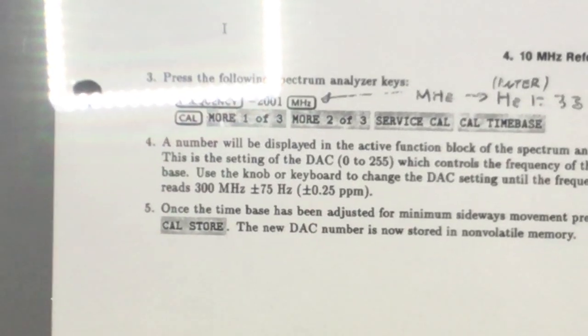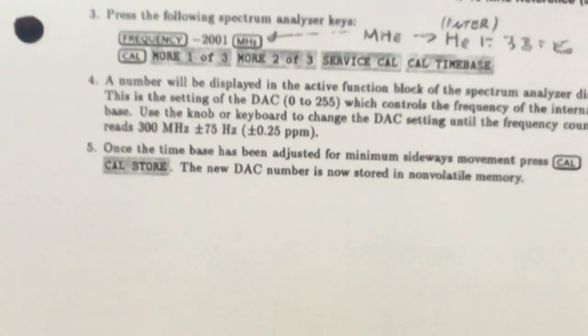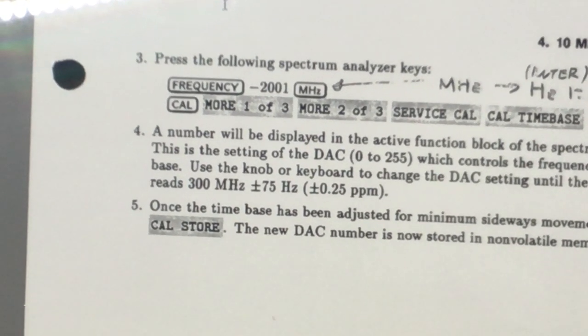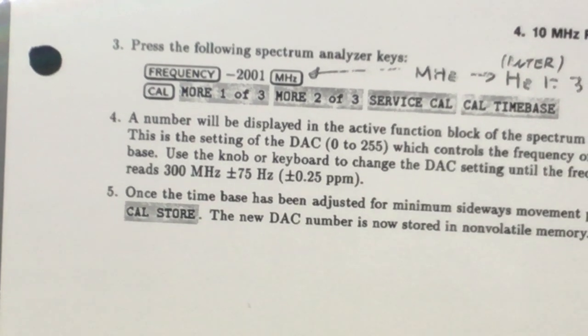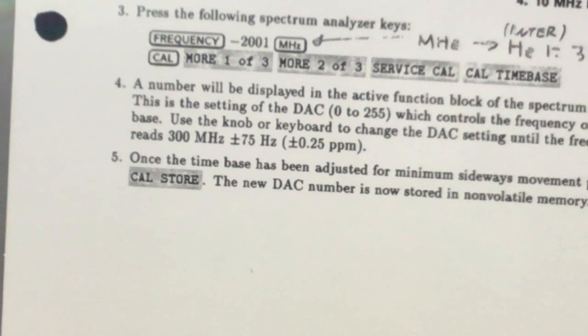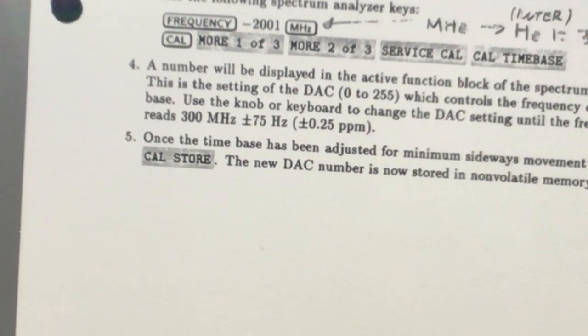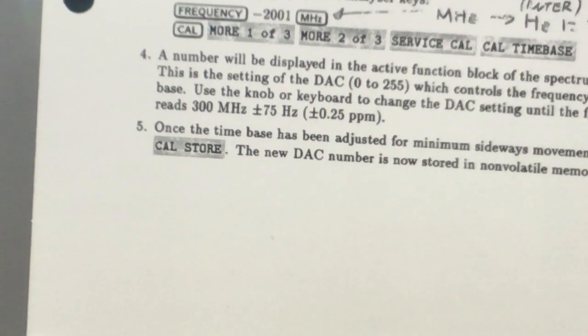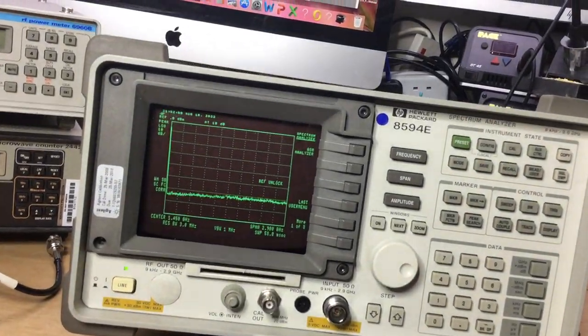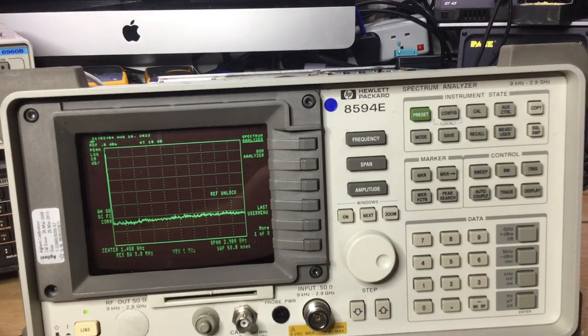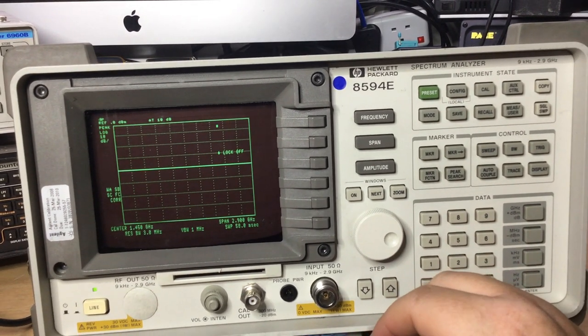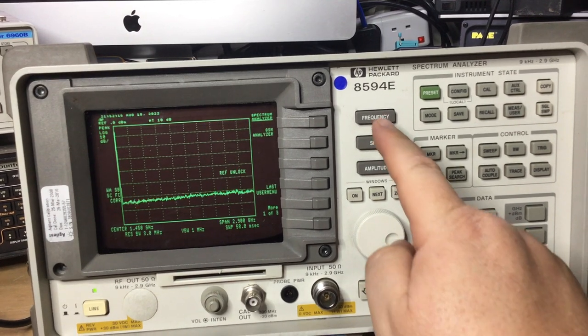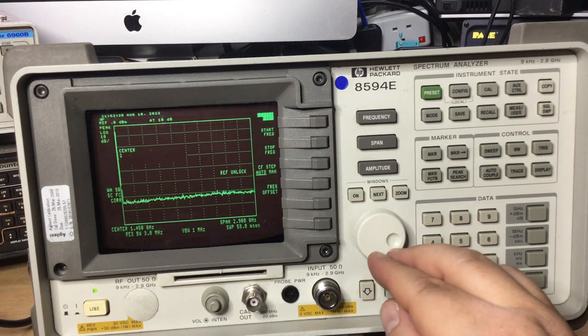Okay, to access the calibrate in the service manual, it talks about using a frequency, excuse me, as a prerequisite, -2001 megahertz. And then going to the service cal and then selecting the time base. Now, when we do that, then a DAC number will appear on the screen and we can adjust that accordingly to then calibrate the frequency. So we'll just look at that now then. So what we'll do, we will enter in a frequency in here. So we'll preset the instrument first, just from where we were in the previous state. Now, it doesn't say hertz or megahertz, that's it. So we'll do frequency. I've already messed it up already.